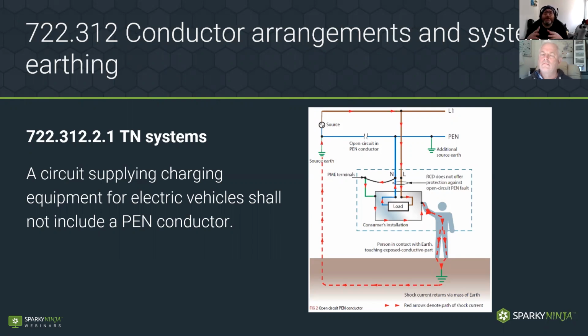Now, this illustration shows the problem that we have with PEN conductors, which we relate mostly to TN-C-S systems. We have the open PEN conductor, not neutral, the protective earth neutral, the combined protective and neutral conductor there. And that creates the problem where once that breaks down, the voltage will rise to earth off of that, and that can obviously create dangerous circumstances. If you've done BS 7671, you'll understand that this is a similar situation in caravan parks and marinas. We just don't take PEN conductors out to plugs that we then would go to a mobile transportable unit, to a caravan, and obviously it's going to be the same for cars.